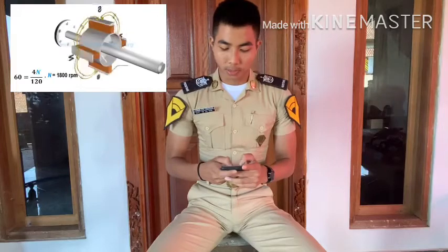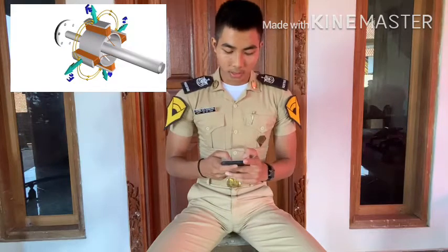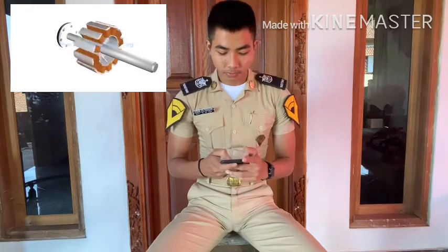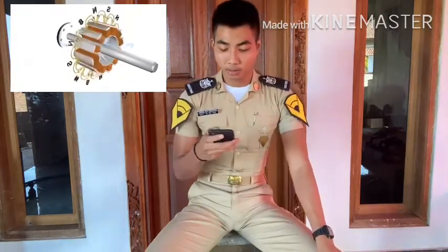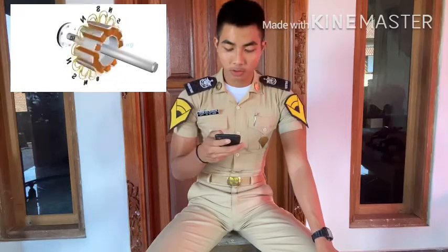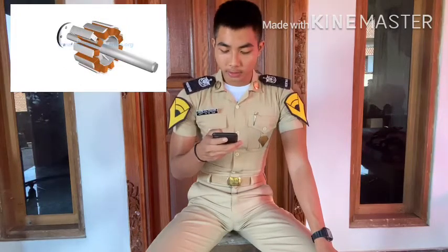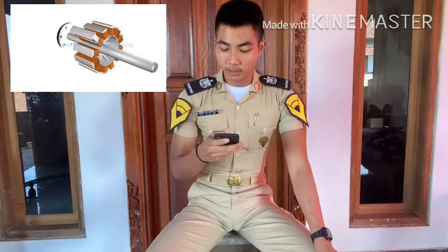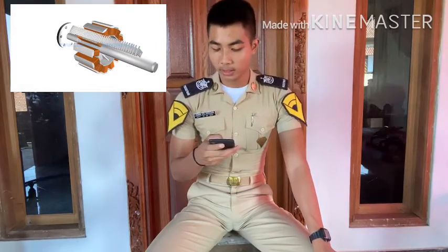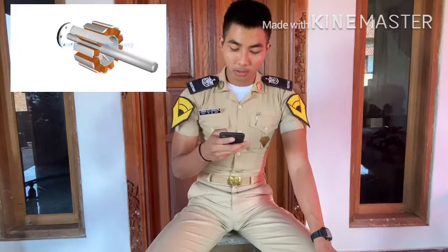Such huge RPM will induce a tremendous centrifugal force on poles of the rotor, and it may fail mechanically over time. So salient pole rotors are generally having 10 to 20 poles, which demands lower RPM. Or salient pole rotors are used when the prime mover rotates at relatively lower RPM. Pole core is used to effectively transfer magnetic flux, and they are made with fairly thick steel lamina. Such insulated lamina reduces energy loss due to eddy current formation.